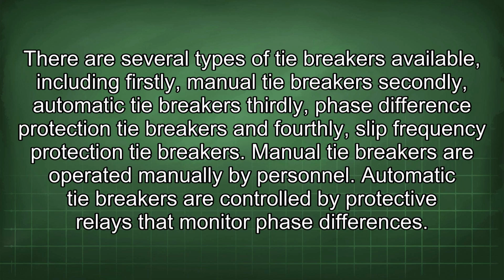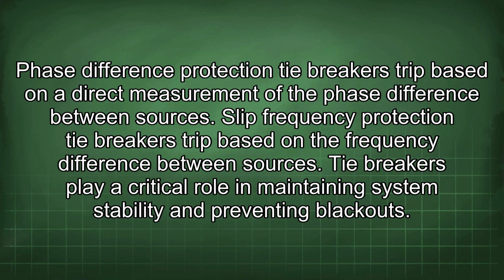There are several types of tie breakers available, including firstly, manual tie breakers; secondly, automatic tie breakers; thirdly, phase difference protection tie breakers; and fourthly, slip frequency protection tie breakers. Manual tie breakers are operated manually by personnel. Automatic tie breakers are controlled by protective relays that monitor phase differences. Phase difference protection tie breakers trip based on a direct measurement of the phase difference between sources. Slip frequency protection tie breakers trip based on the frequency difference between sources.